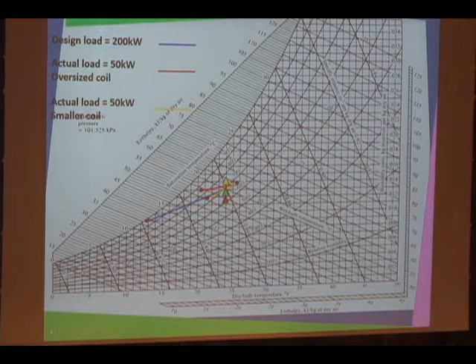So what's the consequence of that? If we use that large coil, the space humidity level goes up. If we were to use a smaller coil, it would come down to this green triangle, and that's where we might get the most effective dehumidifying performance of the same existing coil. We are talking about an oversized coil being able to achieve what we want in practice. How can we do that? We call this the adaptable coil approach, or adaptable coil strategy.